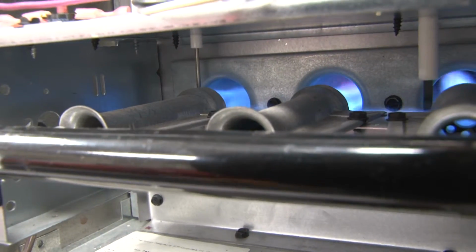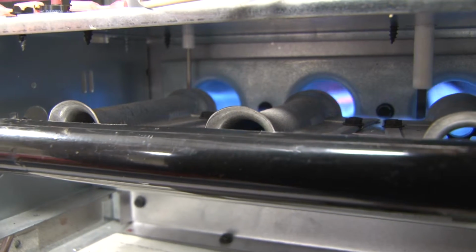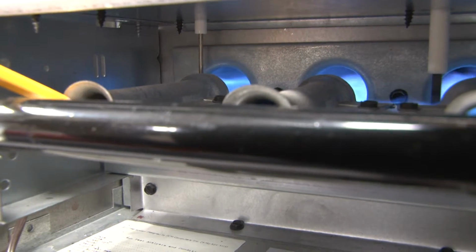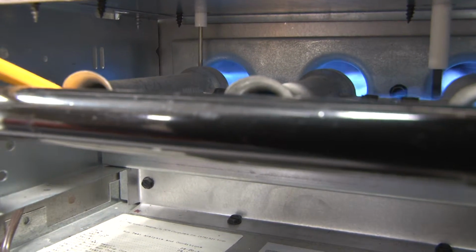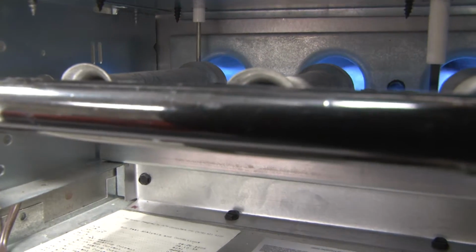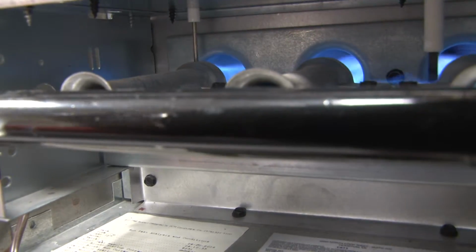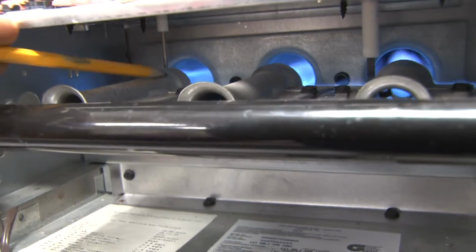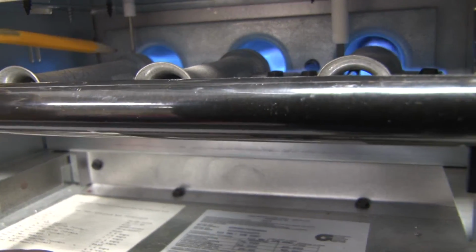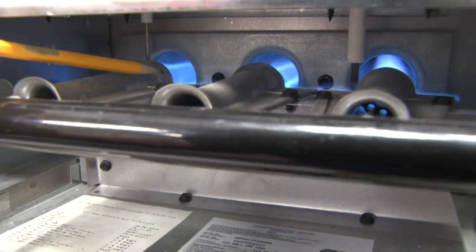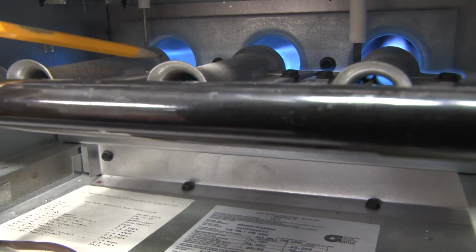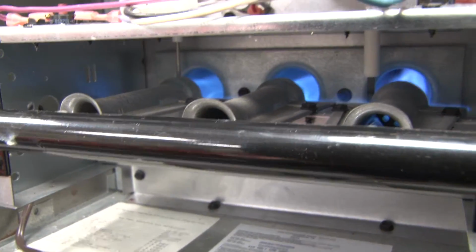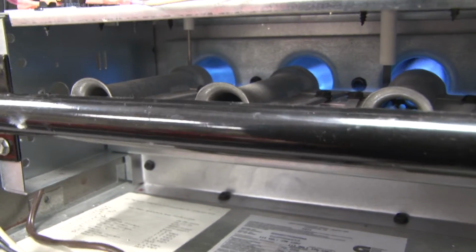Now we see complete combustion using primary air mixing with the fuel. If you notice, I'm moving the pin around the side of where it's mixing. You can see that it's not burning completely because I'm stopping some of the mixture. But as it mixes inside of the burner, it will ignite on the outside, and then it will use additional air, what we call secondary air, to help it burn completely. So complete combustion when there's the proper fuel and air mixture.